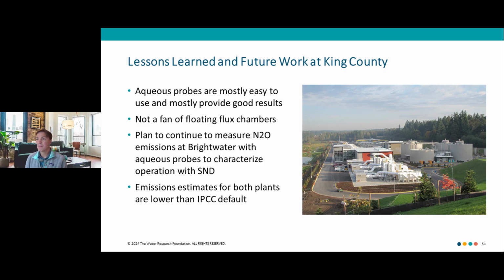Some lessons learned. The aqueous probes are pretty easy to use. They don't require real frequent calibration. They have very good relative measurements, so you can track your emissions through time. The absolute measurement we saw at Brightwater needed an adjustment factor, but otherwise I think they'd be very good for control because of that. The relative tracking is very good. The one small drawback: the probe tip on the unit is glass, the membrane is glass. That can be delicate, I know from experience. And calibrating in really high or really cold temperatures is difficult because you have to calibrate it in a water bath that's at your process temperature, and that can be somewhat difficult when it's really cold or hot.